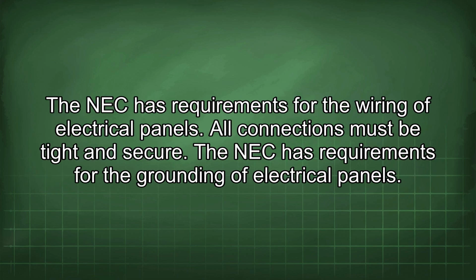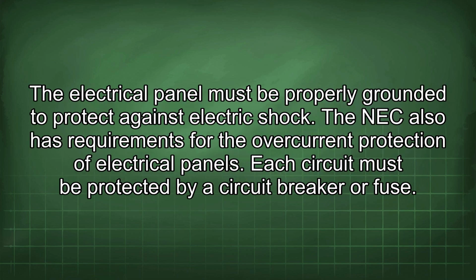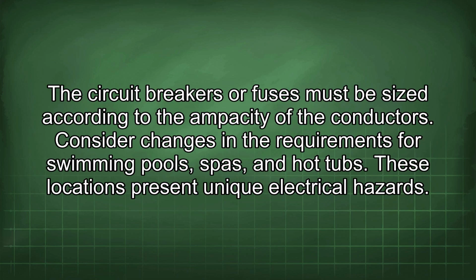The NEC has requirements for the wiring of electrical panels. All connections must be tight and secure. The NEC has requirements for the grounding of electrical panels. The electrical panel must be properly grounded to protect against electric shock. The NEC also has requirements for the overcurrent protection of electrical panels. Each circuit must be protected by a circuit breaker or fuse. The circuit breakers or fuses must be sized according to the ampacity of the conductors.